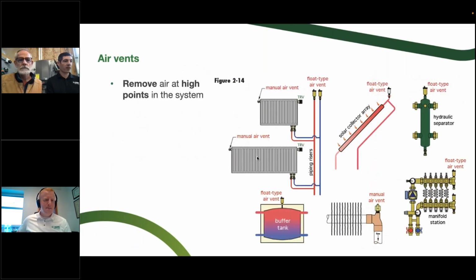Okay, so let's first talk about a high point air vent. So here are some different places where you might find a high point air vent. They are going to be great at getting air out of a system when it has slowed down. Maybe the circulators are off, so there's not a lot of turbulence and the air is going to be more buoyant and find a high spot. So it's great to have a high point air vent in all of these different applications. It could be on the top of a riser, or the top of a solar panel, a hydro separator, anything like that. But it is only going to catch stuff that's going to end up at a high point.